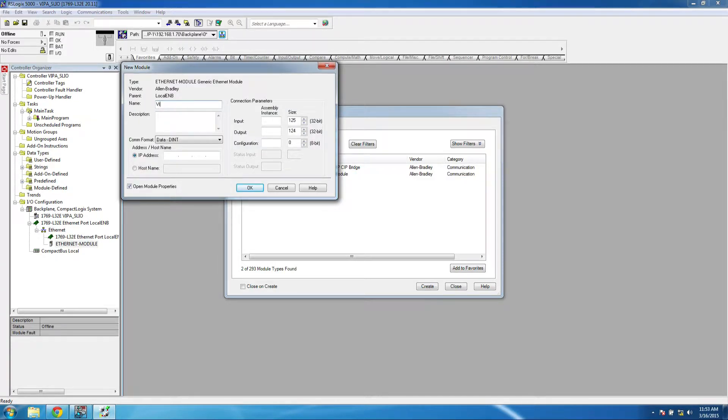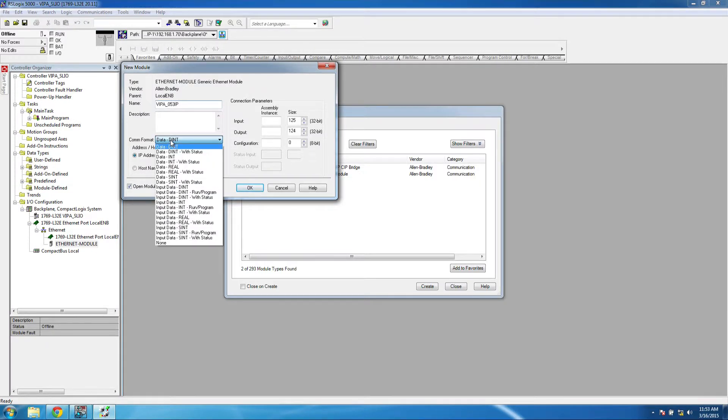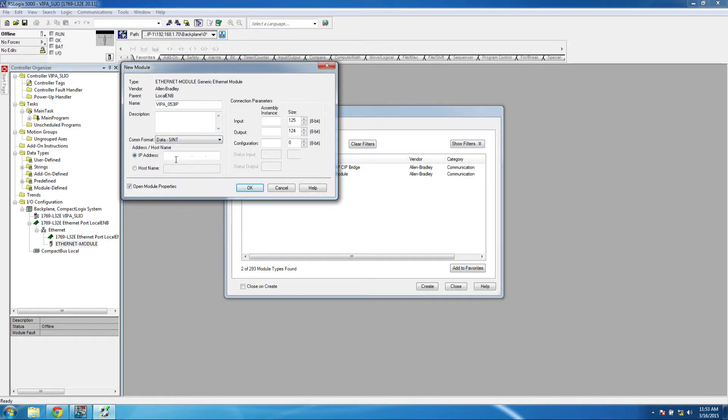In here, we can give this any name. We'll just call this Vipa 053 IP. The COM format, we're going to set to single integer. In this box, we'll enter in the IP address of the bus coupler.